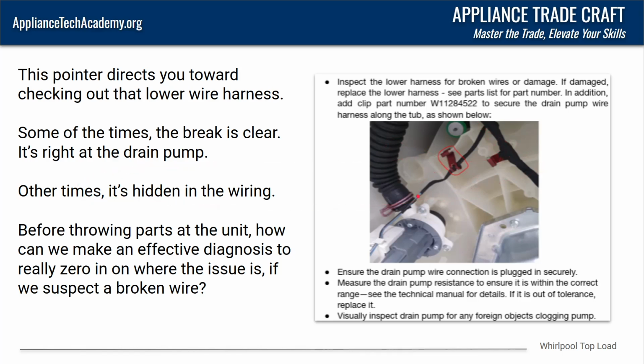And that's why I always prefer the meter tests over a visual test. Sometimes a visual test will show you what it is, but if it's not and you start replacing parts just to find out there's a broken wire right up here, then you've wasted a lot of time and money on that. So before throwing parts at the unit, how can we make effective diagnostics to actually really zero in on where the issue is if we do suspect a broken wire? And we're really going to dive into that here in a moment.